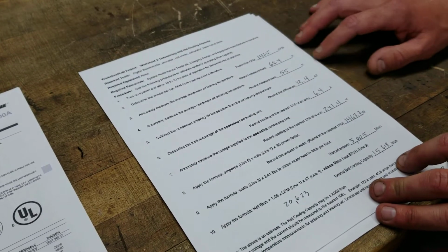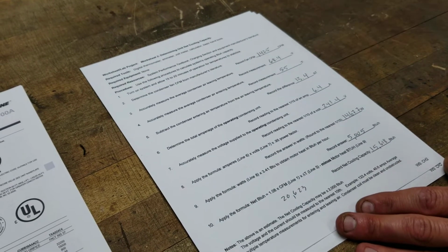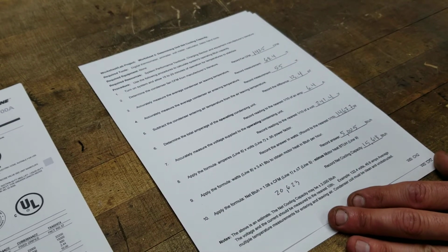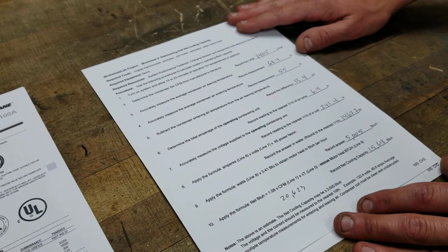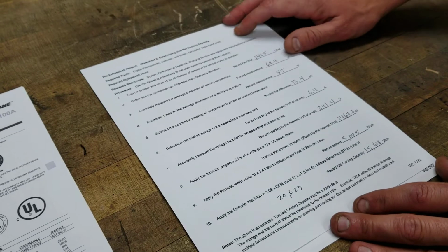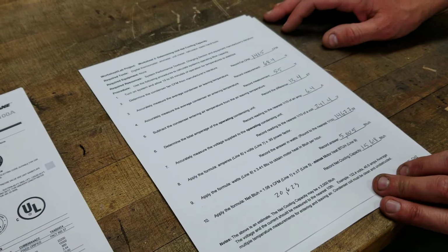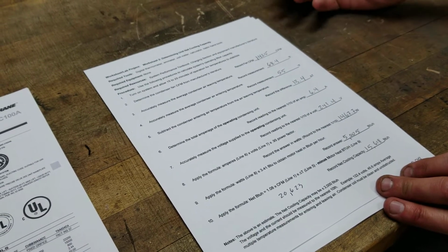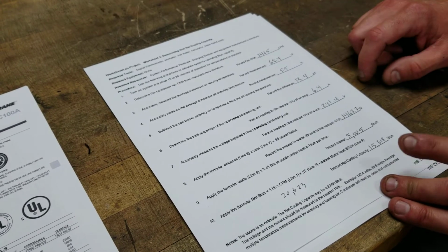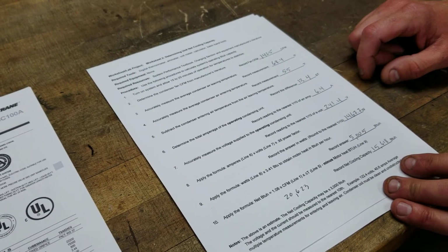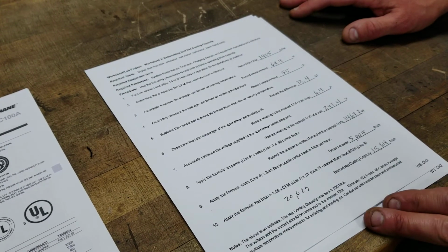And again, if you guys look at the temperatures, it's 55 degrees outside, so in the real world, when we do this test, we should be shooting for at least 65 outside. But just to give you guys an example of checking the net cooling capacity, just by measuring some temperatures. If you've got a thermometer and an amp clamp voltmeter, and a little bit of math, you can come up with a guesstimation of how much cooling capacity your condensing unit is producing.